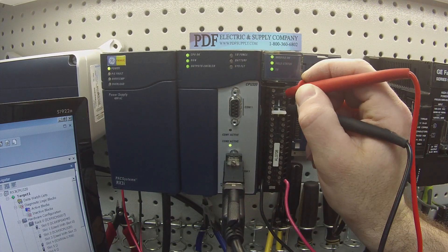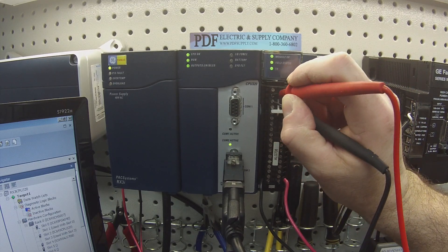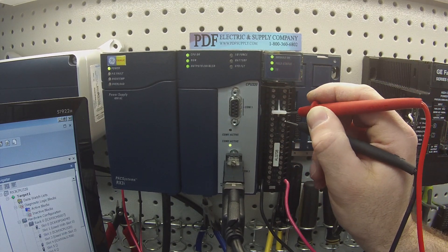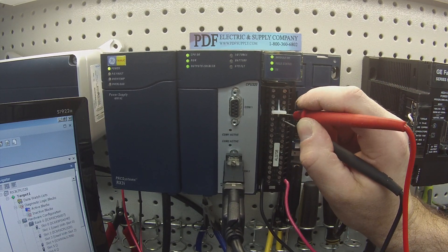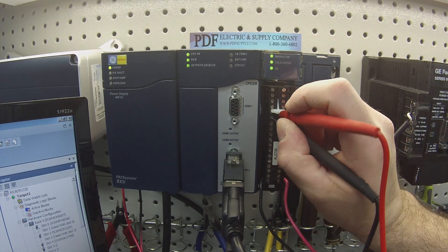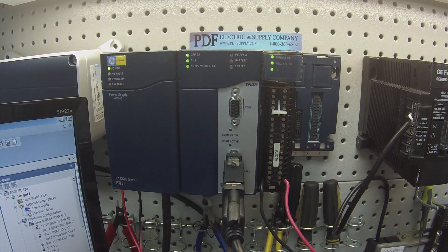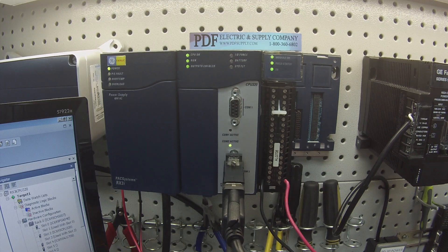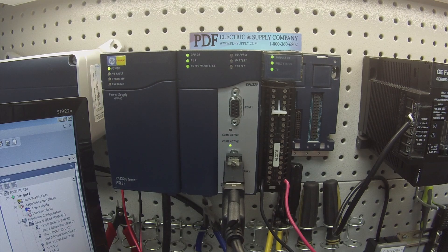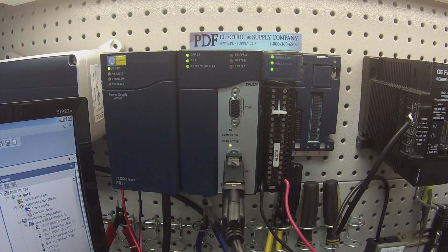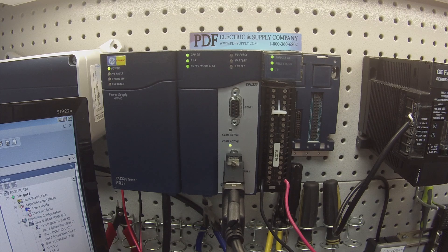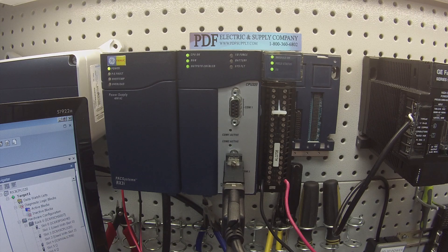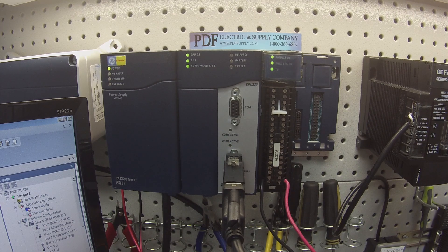Same thing, you want to check for stability. You want to check for full value. All the channels that I have are working perfectly. You want to go through and test all eight channels, both sides. Last channel is ending on channel eight is ending on terminals 12 and 11, or 11 positive, 12 negative.